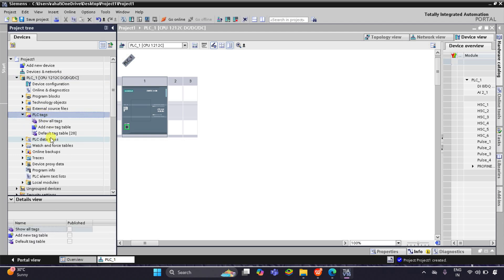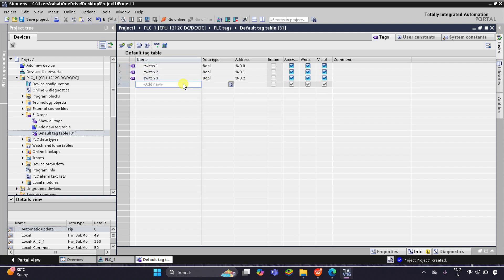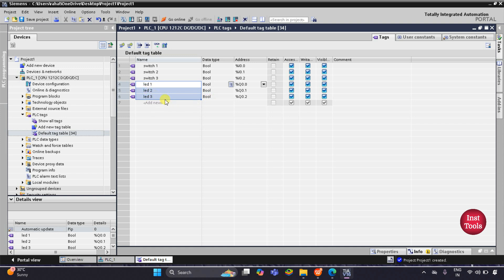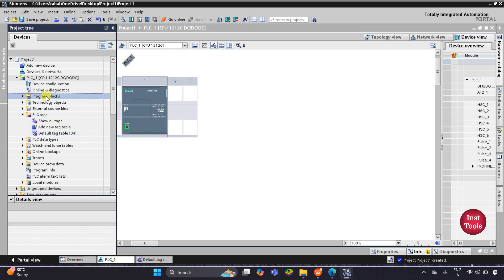I'll go to PLC Tags and the default tag table. Here I will add inputs: Switch 1, Switch 2, and Switch 3. I'll click and drag so that Switch 2 and Switch 3 are automatically fetched. Then I need to add outputs — LED 1, LED 2, and LED 3. For LED 1 I'll set the address to Q0.0, and then LED 2 and LED 3 are fetched automatically. After that I'll minimize the PLC tag table, go to Program Blocks, and then Main OB.